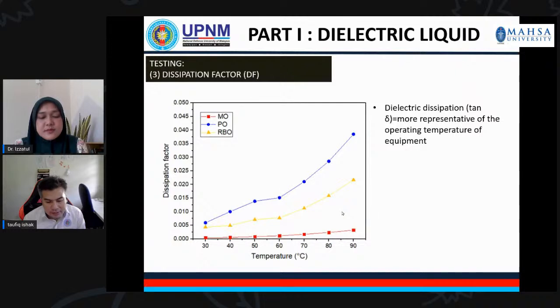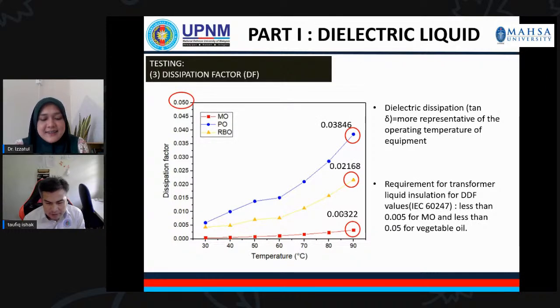Okay, the third test is the dielectric properties test. Any insulation material needs to pass this test, especially the dissipation factor. The dissipation factor is the property that indicates how much energy is dissipated through the liquid as heat.